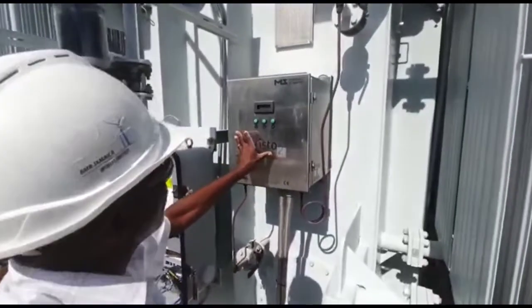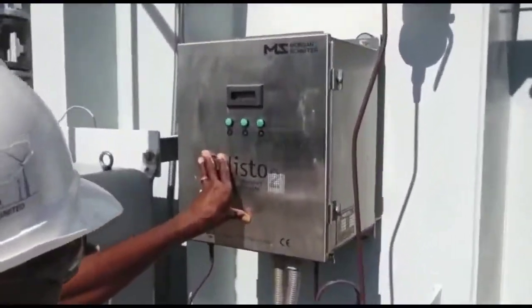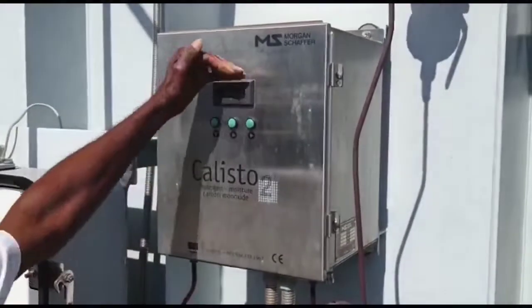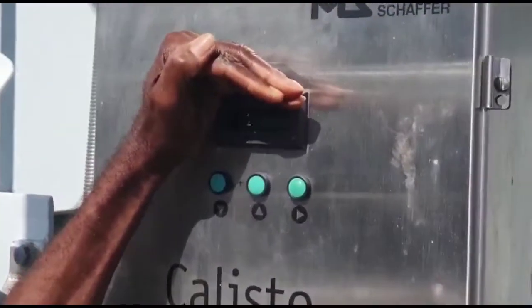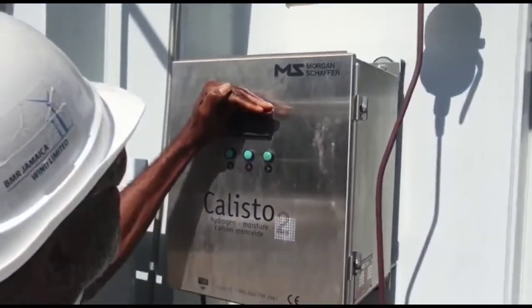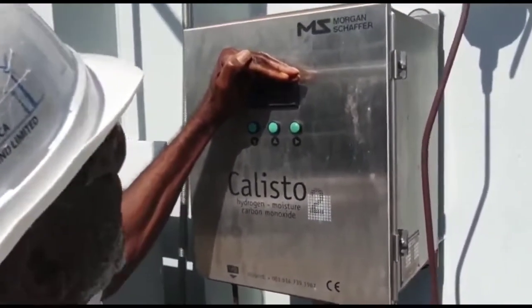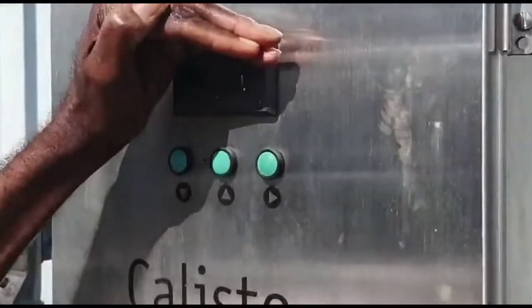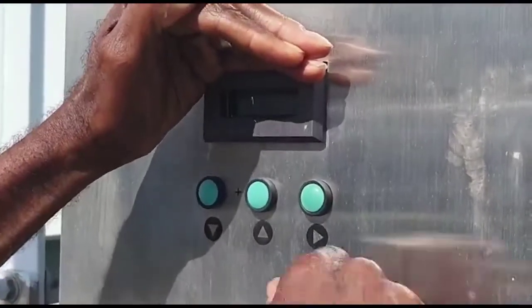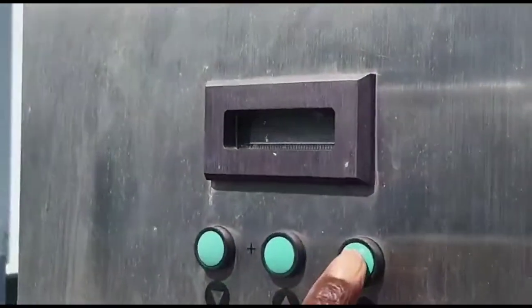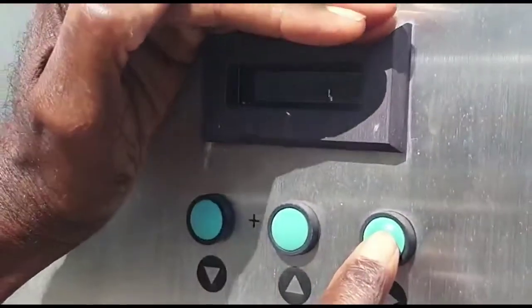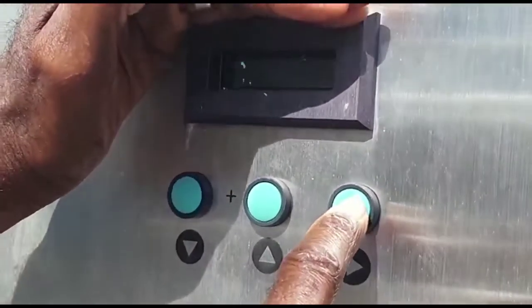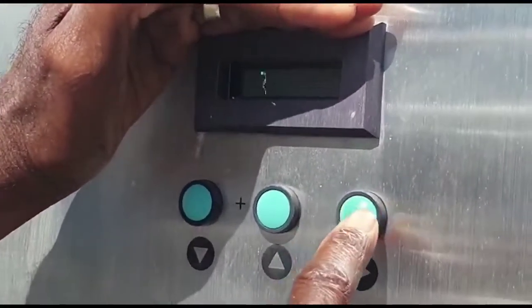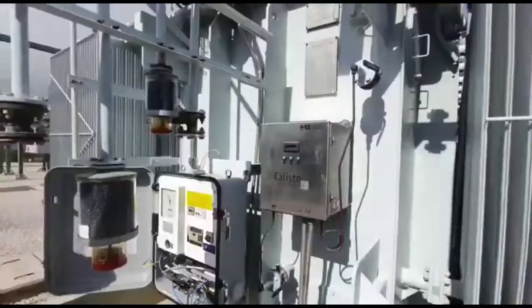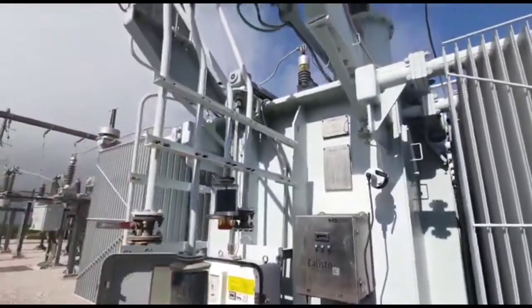This unit is used to give us an online measurement of the gases that are in the oil. Right now we're showing H2 as hydrogen, which is lower than the dissolved limit. And if you want to see the other gases, you press this button and it scrolls through the other parameters like carbon monoxide and water content. On top there is the storage tank that stores the oil for the transformer.